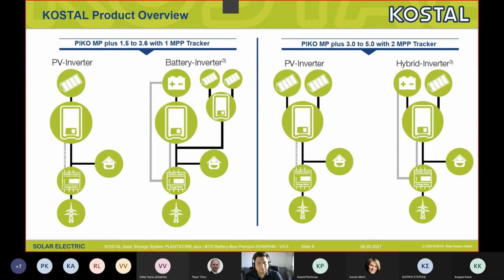In the single MPPT tracker, you can connect only batteries in order to support an existing photovoltaic installation. As you can see in the picture, we have an existing installation with another PIKO MP Plus or another inverter, doesn't matter. The AC side is connected to the PIKO MP Plus battery inverter, so we are charging the batteries from the existing PV installation. During the night or days without sun irradiation, we take advantage of the fully charged batteries for our consumption.